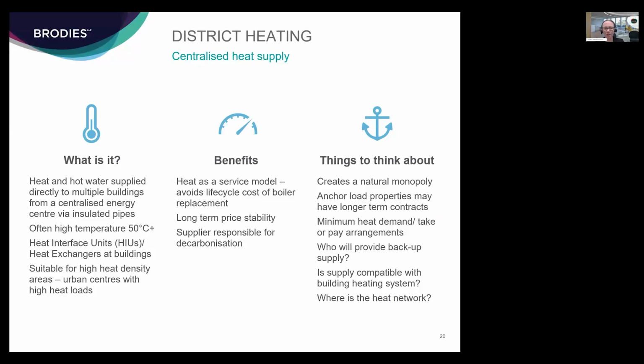This is the most centralised option and involves heat and hot water supply directly to multiple buildings from a centralised energy centre using insulated pipes. This is often higher temperature, so 50 degrees plus. So you have heat interface units or heat exchangers, depending on scale, at buildings. These are suitable for high heat density areas such as urban centres with high heat loads, and examples would be Aberdeen Heat and Power or the Glenrothes Energy Network.